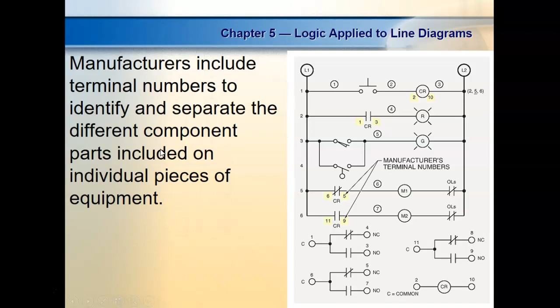So you got a control relay, you have 2 and 10 that energize that relay. Okay? And then it comes over here and tells you 1 and 3 are used here, 6 and 5 here, 11 and 9 here. This is your typical setup for a control relay. So 1 and 3 should be normally open, 6 and 5 should be normally closed, and 11 and 9 is normally open. Okay.